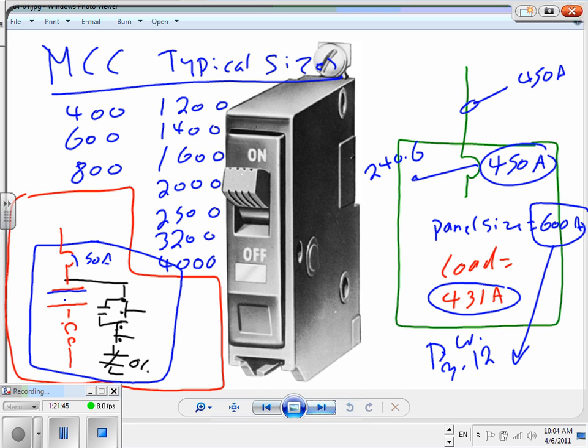And you have push buttons, guys, the push button start, stop. Lights, they have some lights on the bucket. So when you draw that bucket, it has a disconnect in it, which is the overcurrent detection device. It has a contactor, a push button start, stop, and some lights, all in one big bucket. Now to fit this one, depending on the size, you're looking at a foot by a foot by a foot, really, of space for a good size NEMA 4 starter. Any question, guys, about this? This one acts as one big bucket inside this MCC.